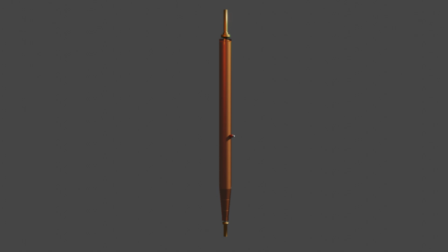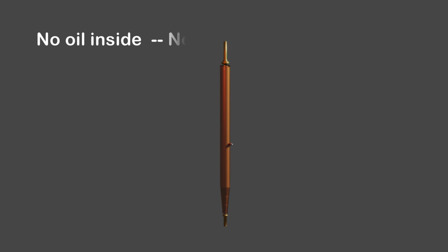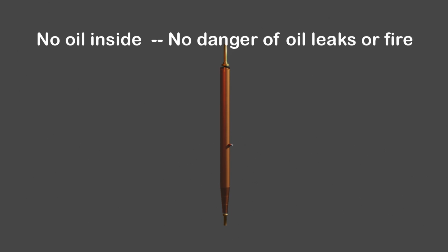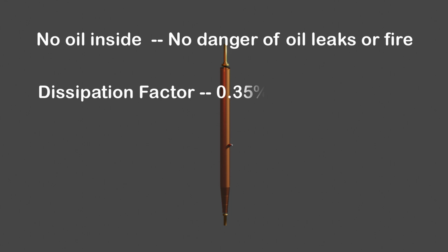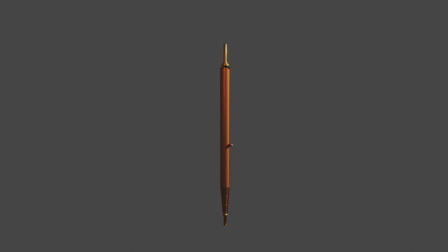The big advantage of this solid insulation is that it is completely dry and very strong. There is no oil inside, so there is no danger of oil leaks or fire. The solid resin also binds the layers tightly, resulting in very low energy loss. For example, our RIP bushings have a tan delta dissipation factor on the order of only 0.35% or lower, which means very little energy is lost as heat in the insulation.